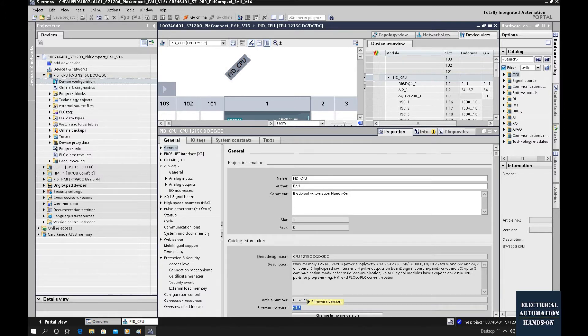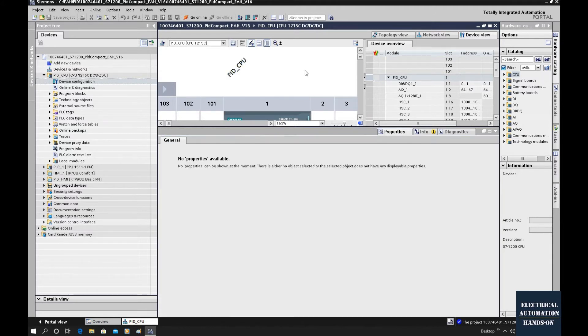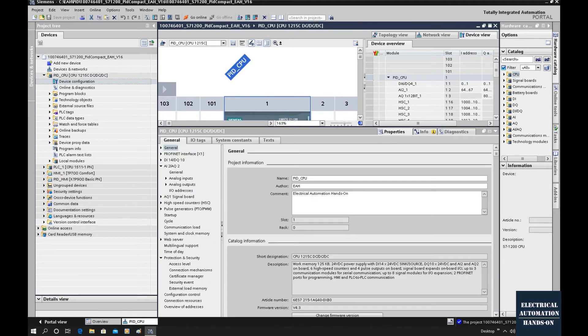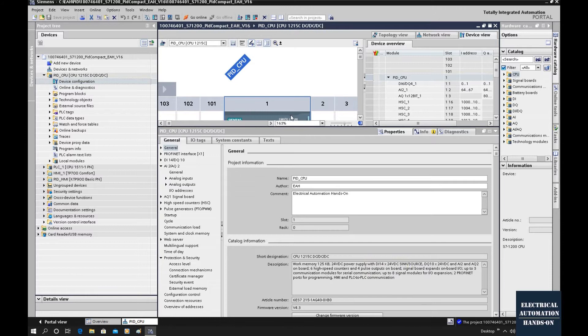For general programming, a 4.3 configuration can still download to higher version hardware without issues. But for enabling special features like the OPC UA server, we must match the configuration and the hardware. For example, my hardware is 4.4, but the configuration is 4.3. So I need to upgrade this 4.3 inside this project to 4.4.